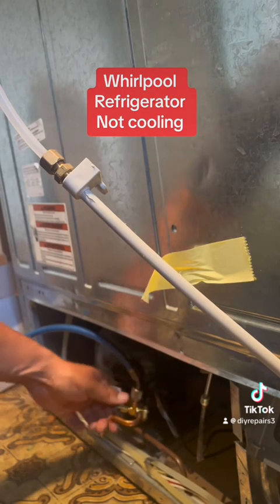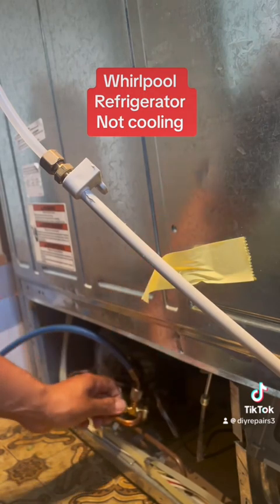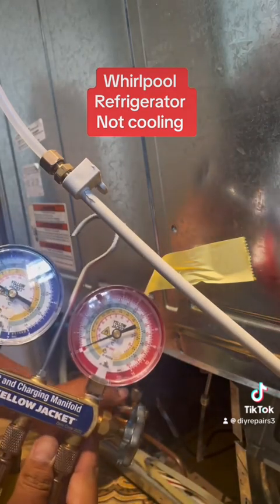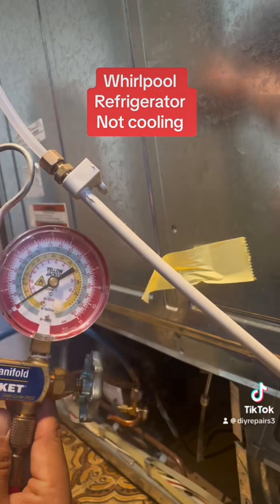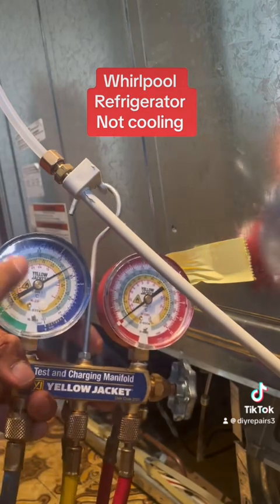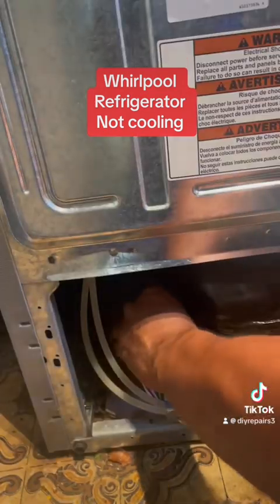That's letting me know there's no leaks — if there's gas. If there was no gas, that means the system has a leak. If you look at the blue gauge — like a little clock — you're going to see it reaching. See, it started moving — look at that move.